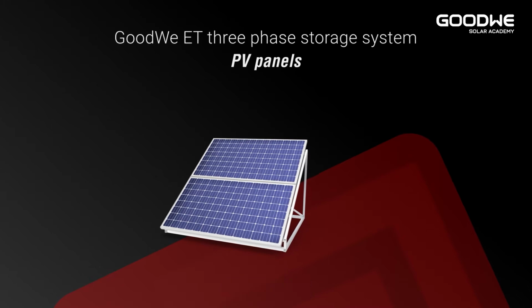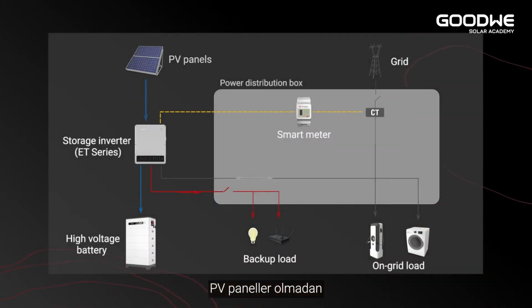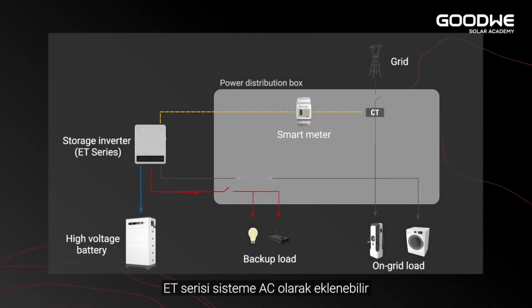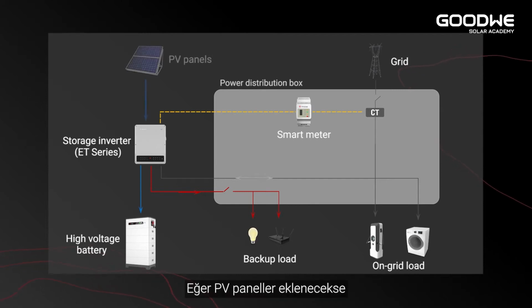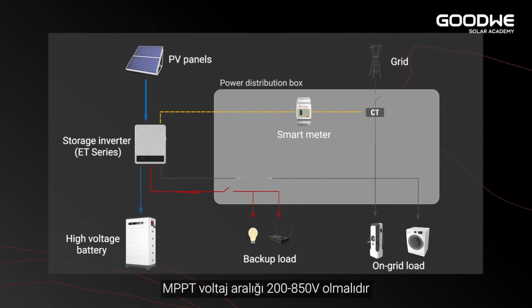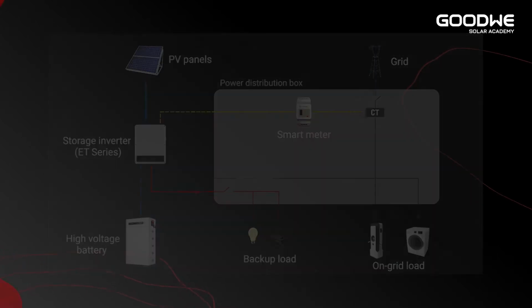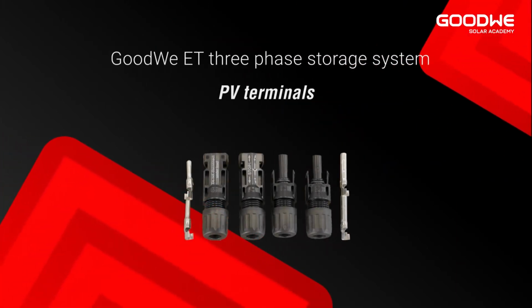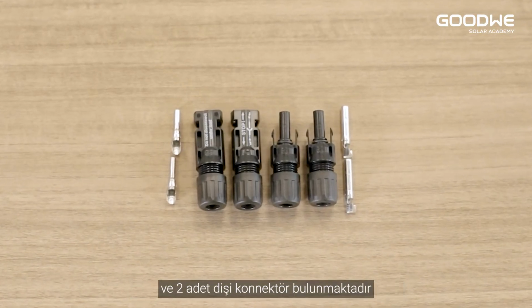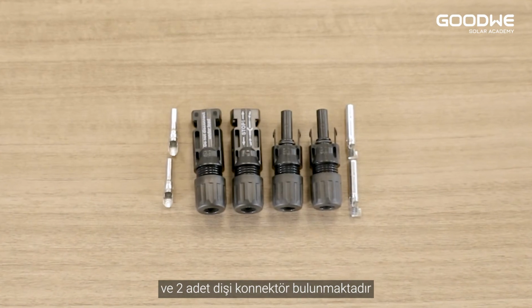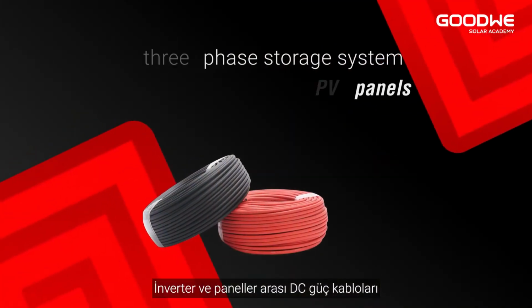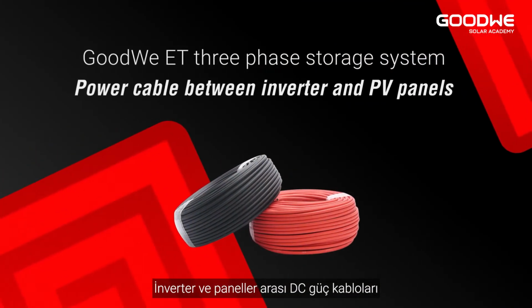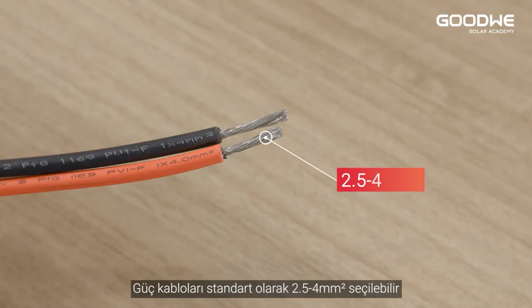PV panels. This is optional. Without the PV panels, this ET storage system is an AC coupled system. If connected to PV panels, the MPPT voltage range is 200 to 850 volts, and the maximum voltage is 1000 volts. PV terminals. GoodWe provides 2 positive terminals and 2 negative terminals in the ET accessory box. Power cable between inverter and PV panels. The power cable should be a standard 2.5 to 4 square millimeter.